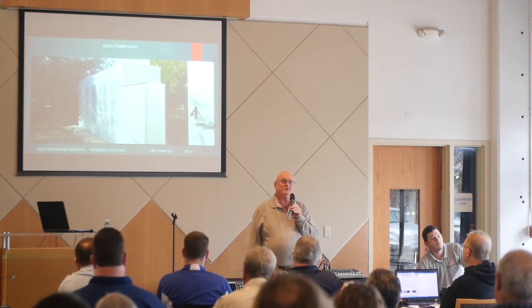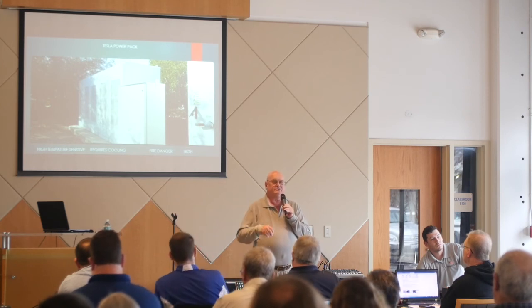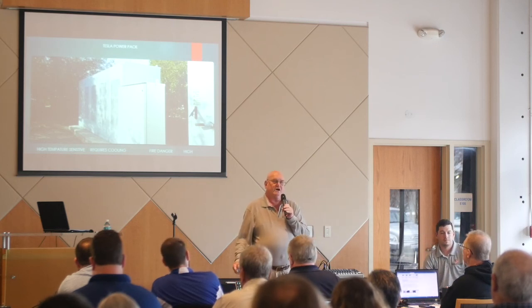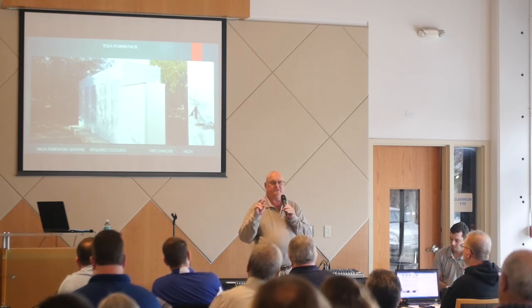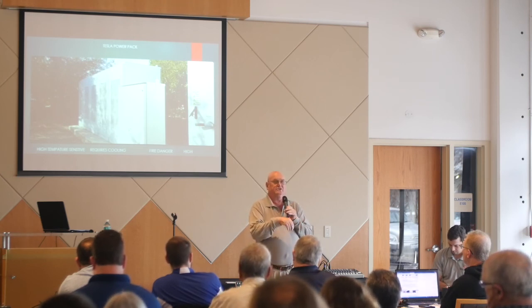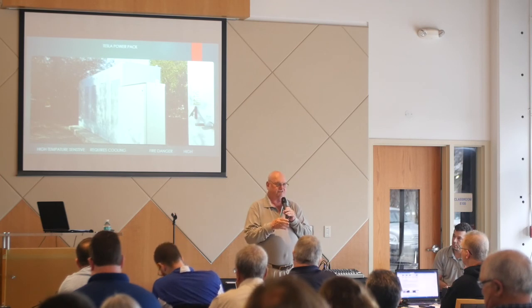So the hydrogen, anybody in here who does controls, and anybody who's working at all around microgrids or an islanded situation knows that there are two things that these situations require. First of all, the transition from, for instance, grid connected to an island mode, you've got to be able to shed loads very rapidly, because you have to be able to buy time for the control system to figure out what's going on. How many of your resources are available to create power and put it back on the stream? Is it day or night?